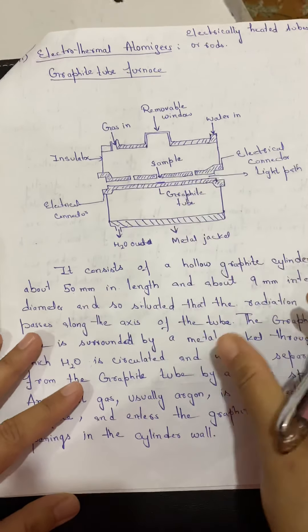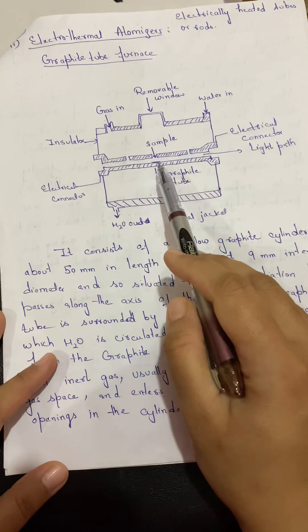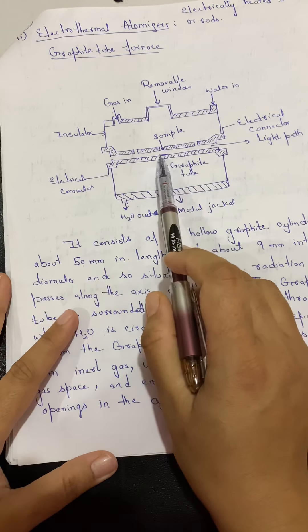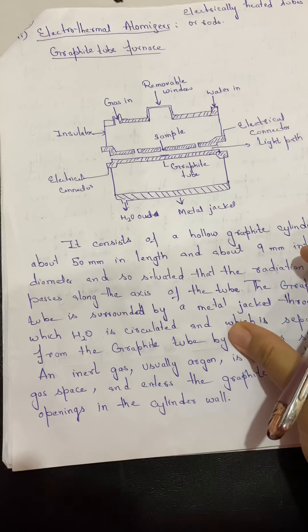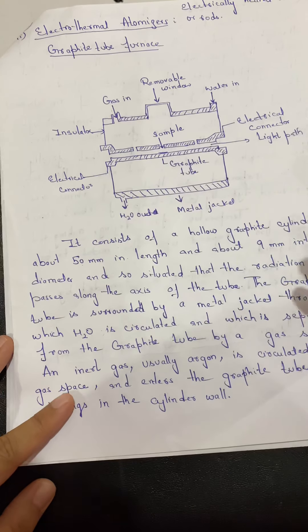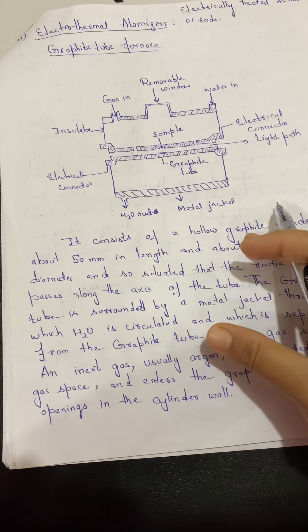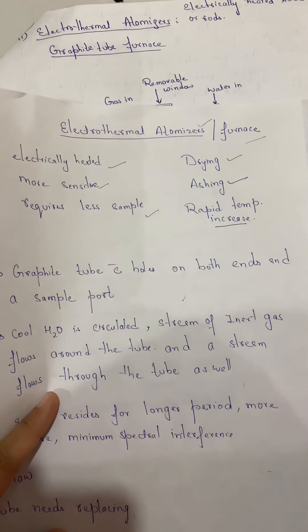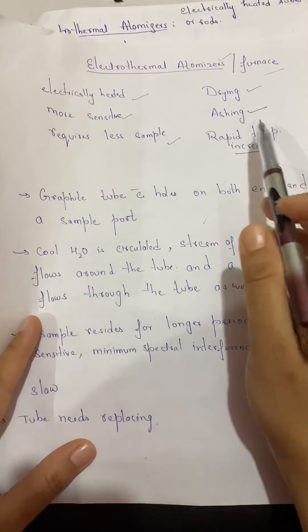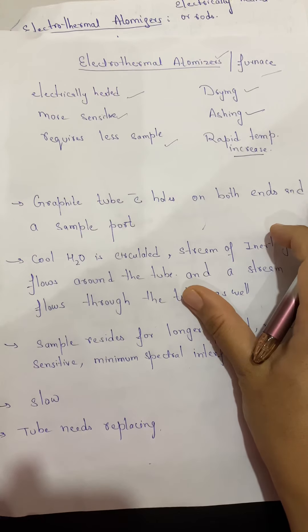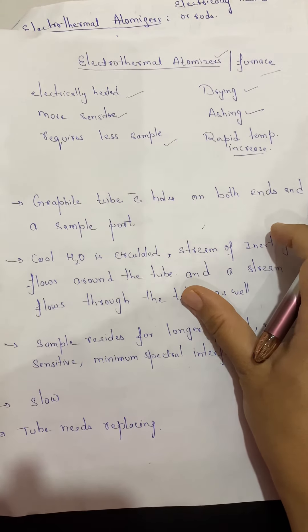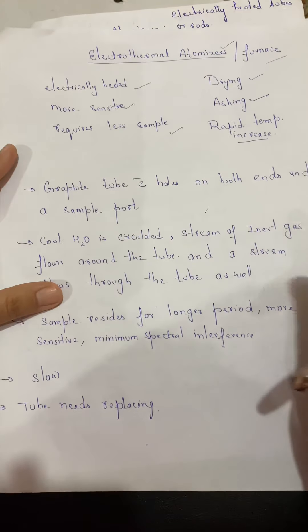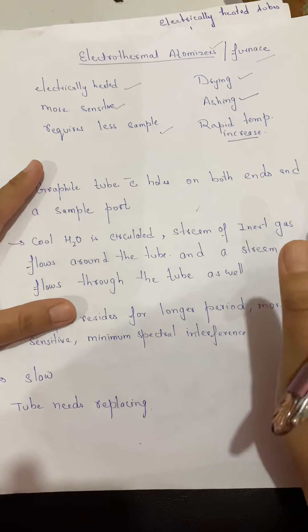When the sample is introduced through the sample port, an electrical connection is provided and the tube starts heating up. The process occurs in different stages. First, drying of the sample takes place — the sample is made absolutely bone dry with no traces of water. The next step is ashing, where the sample is completely ashed: oxides and other components are combusted so that nothing remains unoxidized.